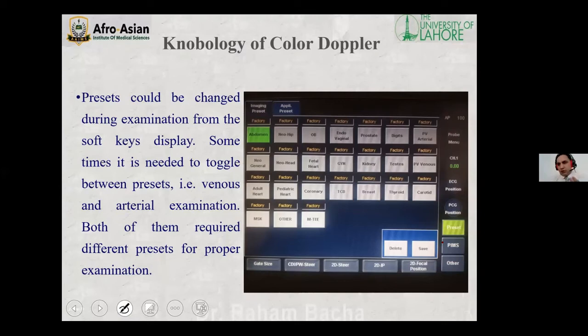For example, sweep speed, and in the same way Doppler frequency, wall filter, dynamic range, internal presets, and so on. So these are too many variables which could be adjusted for every protocol. So that is why it is important to select the proper protocol.